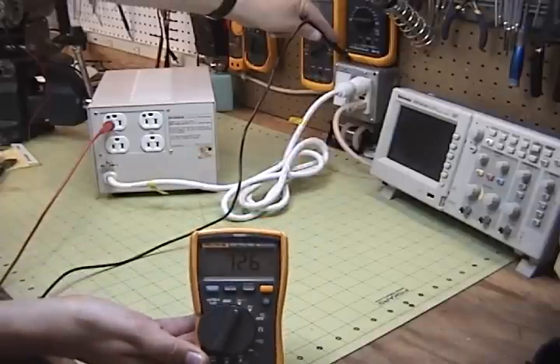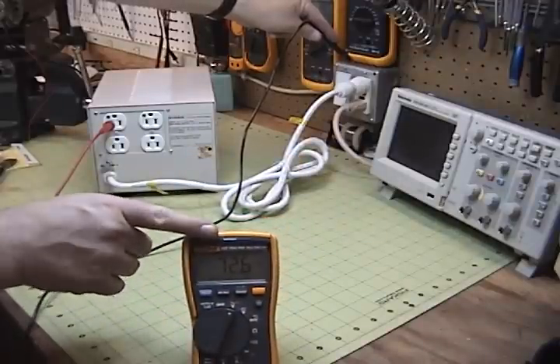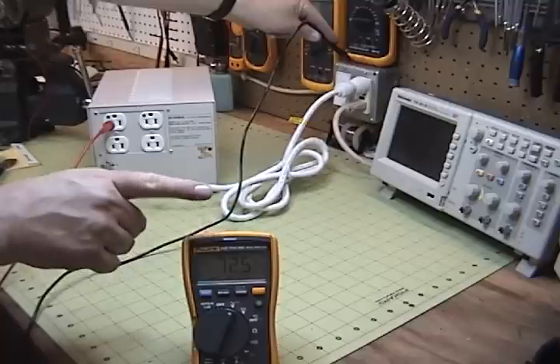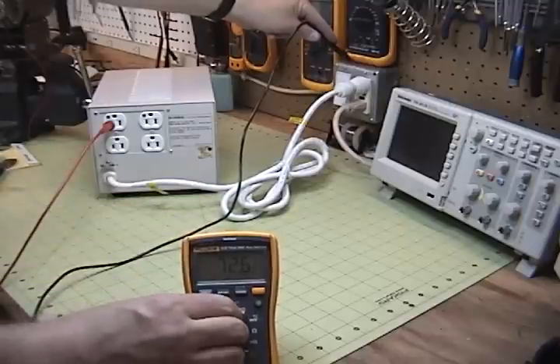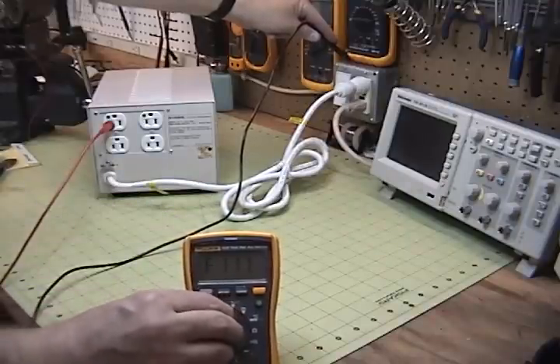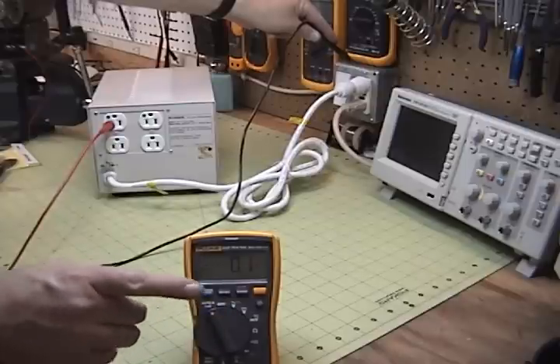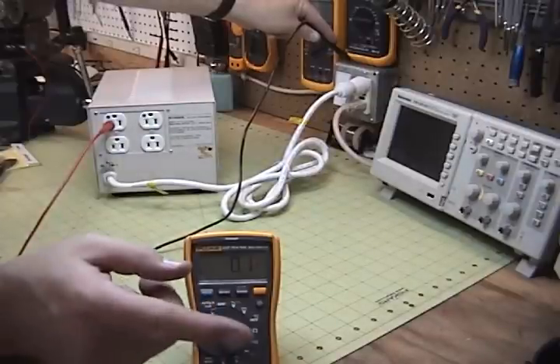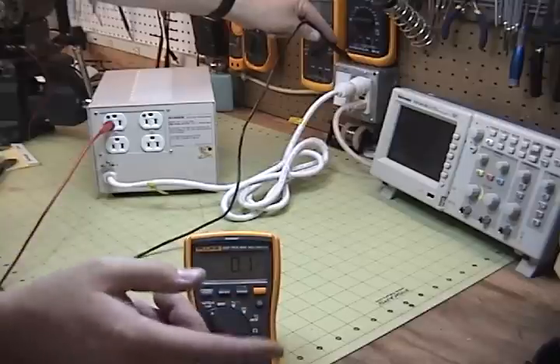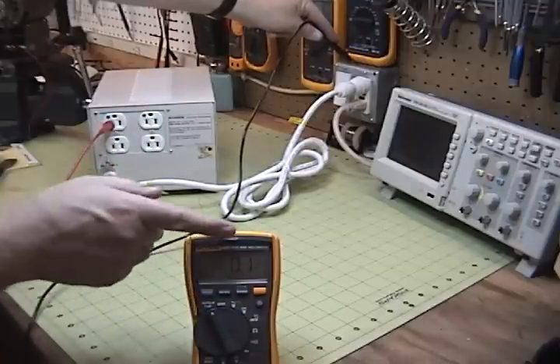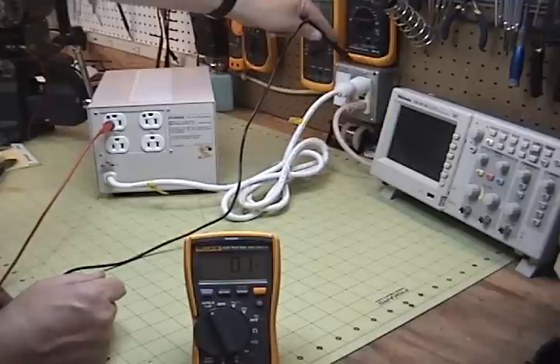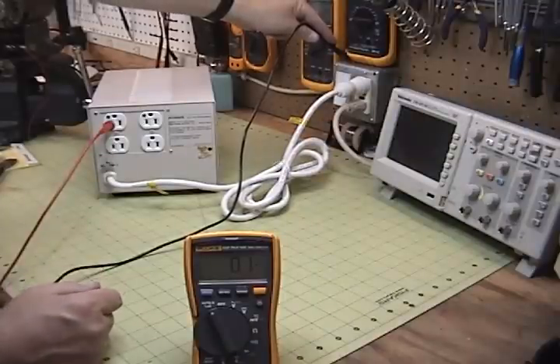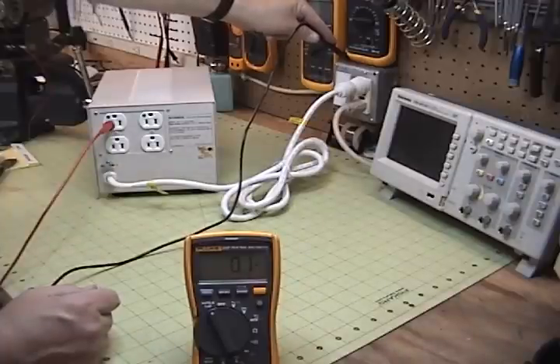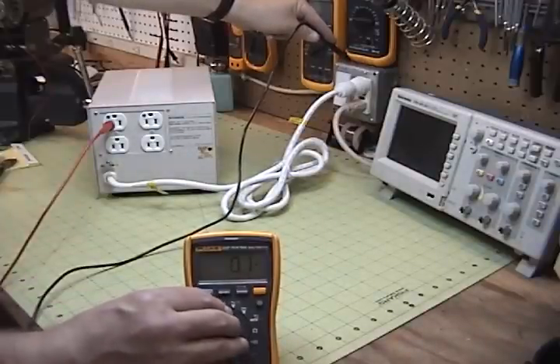To prove it, we have a 117 fluke electrician's meter, which has what's called a low Z, a low auto Z, which will measure the voltage without those ghost voltages. Electricians need it to test stuff, and I need it to test a transformer. You can see it's reading 0.1 volts as the actual voltage that's there. So that ghost voltage isn't really there, and it won't be a problem for an oscilloscope either.